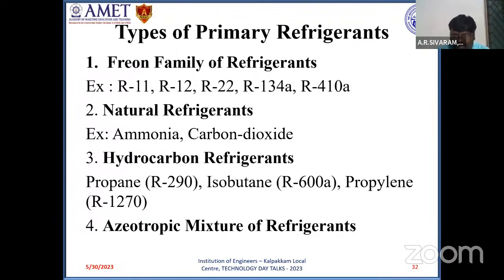Next, coming to different types of primary refrigerants. Freon family of refrigerants: almost 80% of the refrigerants which we use in our day-to-day life, ranging from domestic to commercial refrigerants, belong to this Freon family. This is the first type, the second type is natural refrigerants, and the third type is hydrocarbon refrigerants. Of course, hydrocarbon refrigerants have a lot of advantages, ranging from zero ozone depletion potential to very low global warming potential. But since they possess the risk of flammability, they have not been commercialized on a large scale. And the last one is the azeotropic mixture of refrigerants, which is not a single refrigerant, but a mixture of two or more refrigerants.